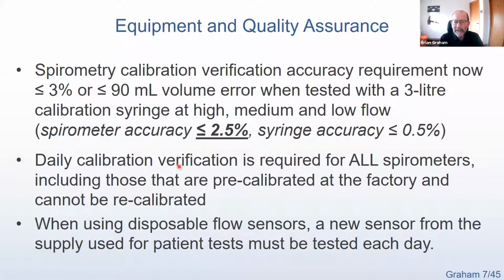The other thing is that daily calibration verification is required for all spirometers, including those that are pre-calibrated at the factory and that cannot be recalibrated in the field. And it really annoys me when I see advertisements for spirometers that say no calibration necessary. Well, you may not be able to calibrate it, but you absolutely must verify that the calibration is working and that the spirometer is measuring what you think it should be measuring. And when you're using disposable flow sensors, you need to use a new flow sensor from the supply used for patient tests each day.